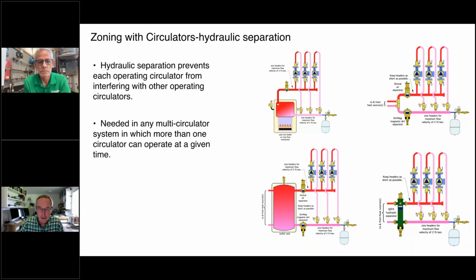Now, yeah, you can argue in here they're not necessarily all common, but these headers should be short. They should be generously sized. A good guideline is that with all the zones operating at their design flow rate, the inlet to the header should not exceed a flow velocity of 2 feet per second. That keeps the head loss very low. So when the head loss through the common piping is kept very low, you will achieve hydraulic separation. And there are several ways to do it. Cast iron boiler systems with zone circulators have always worked, assuming the headers have been kept short and generously sized. And honestly, I have seen systems where that was not true, where somebody put like 6 zones in and used a 3/4 inch copper header for it.